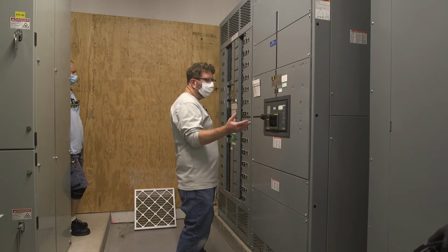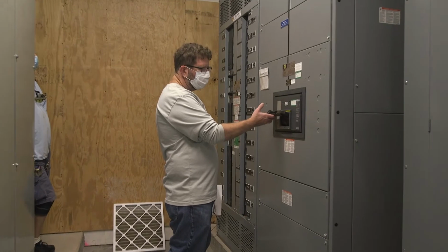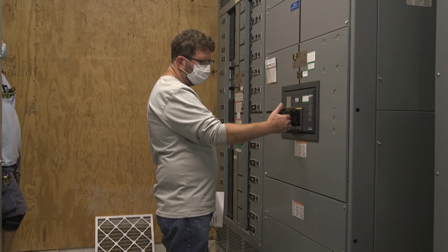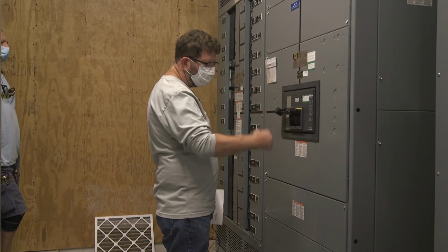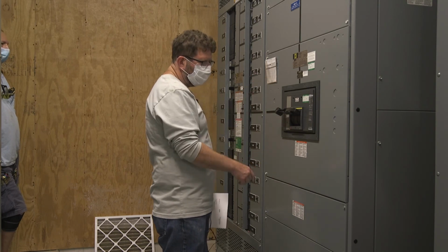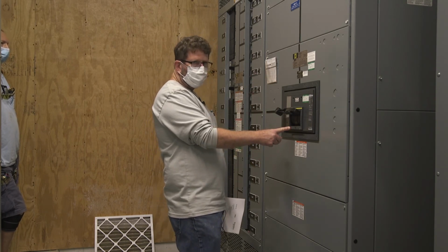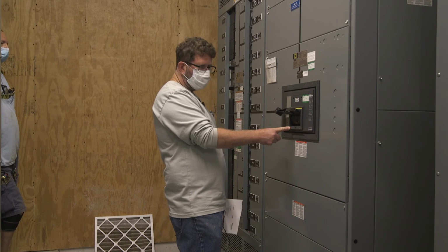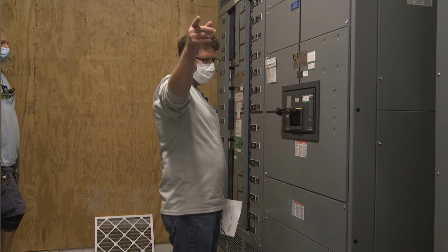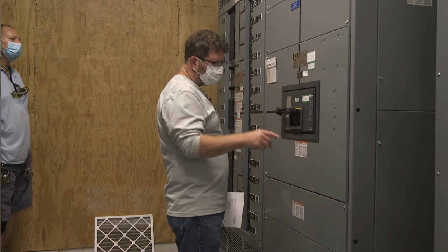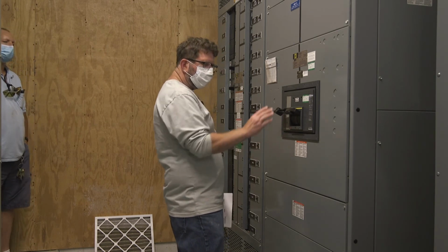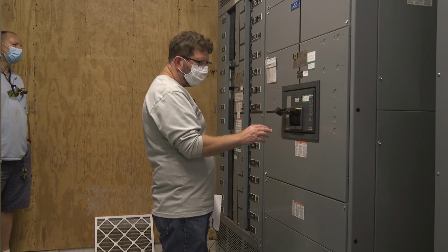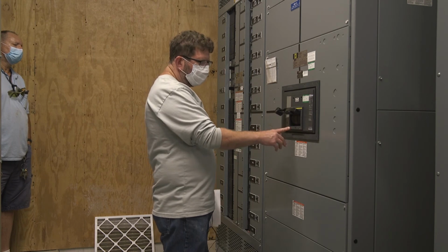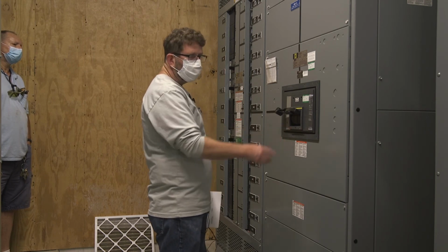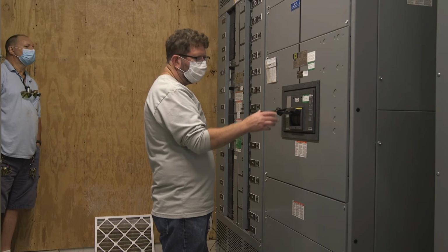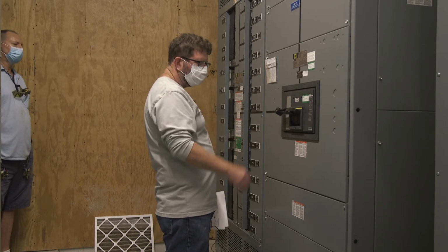This is more like a typical breaker. Right here it's closed. If it trips, it's going to go into mid position. To reset it, open it all the way up, and then close it. There's a push to trip. This just exercises the mechanical trip. That white button on the Masterpact breaker sent a signal into the trip unit to simulate a ground fault, so it was an electrical trip. This is just mechanical. If you're going through and working on these, we recommend exercising them once a year still.